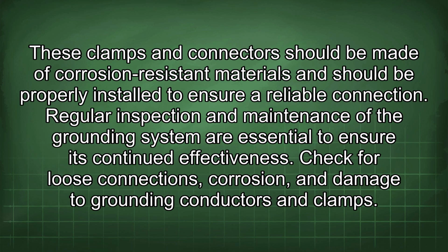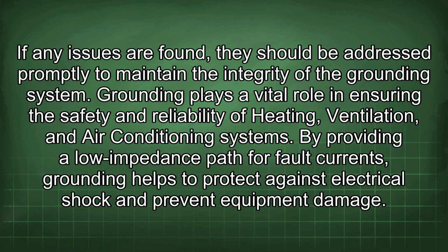These clamps and connectors should be made of corrosion-resistant materials and should be properly installed to ensure a reliable connection. Regular inspection and maintenance of the grounding system are essential to ensure its continued effectiveness. Check for loose connections, corrosion, and damage to grounding conductors and clamps. If any issues are found, they should be addressed promptly to maintain the integrity of the grounding system.